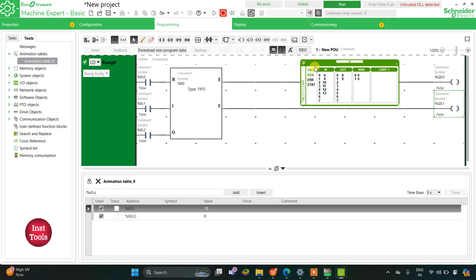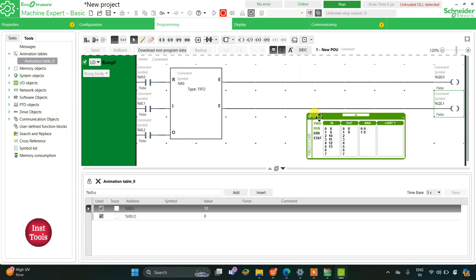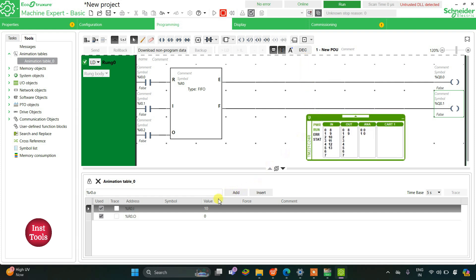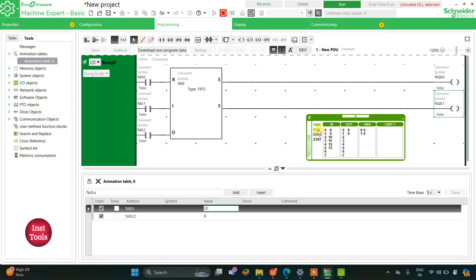I will feed two or three more elements here. The second element I will feed is... you need to remember the first one we have entered 10 as a first feed. I will give another that is 20 and then enter. Then again toggle I0.1 on and off.